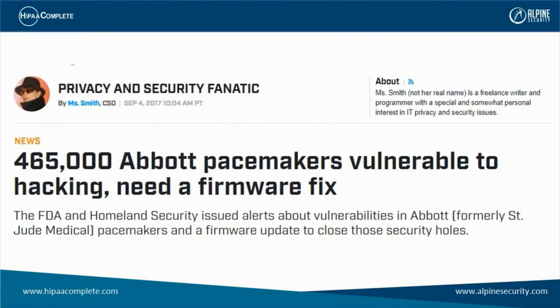As an example, with the Abbott pacemakers, there were almost 500,000 of these that had a vulnerability, and the vulnerability allowed someone to remotely connect to the pacemaker and alter the rhythm and alter its functionality. And if you think about it, the fix is a firmware fix, but the firmware fix is applied wirelessly to an unsecure pacemaker. If someone can wirelessly apply a firmware fix to an implantable pacemaker, then that same mechanism could be used to plant malicious software instead of the firmware.